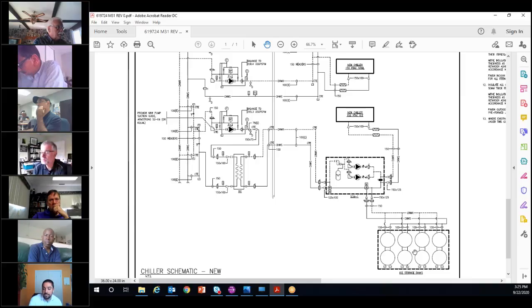And then during the day or whenever, again, your strategy is to use that stored cooling capacity, you then pump glycol through that system and you slowly melt the ice on the outside of the tubes, which of course cools your chilled water. So these 8 tanks here are essentially equivalent to about a 150 to 200 ton chiller, depending again on how quickly you want to melt the ice. Just like an electric battery would be measured in kilowatt hours, a thermal battery like this is measured in ton hours. So 1 tank may be 150 ton hours, so 8 tanks may be 1,200 ton hours. So if you melt that over an 8-hour span, you essentially have a 150 ton chiller for 8 hours. And then of course there is some flexibility and resiliency in the system for how that can be operated.